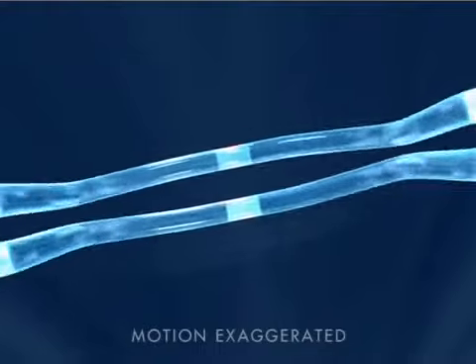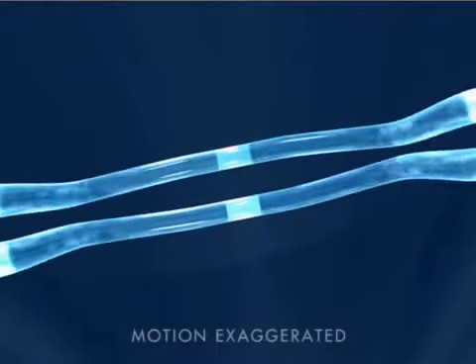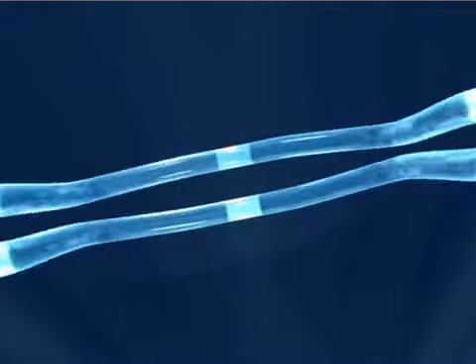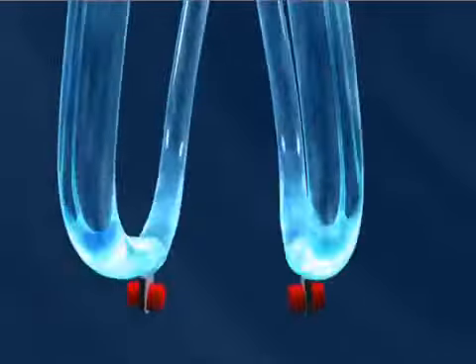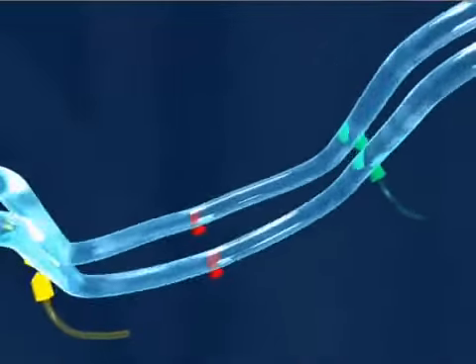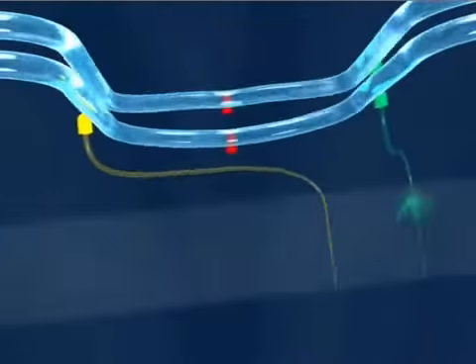But when a mass flows through the tubes, the tubes deform proportionally to the mass flow rate. This deformation is registered by two sensors and forms the basis of the measuring result.